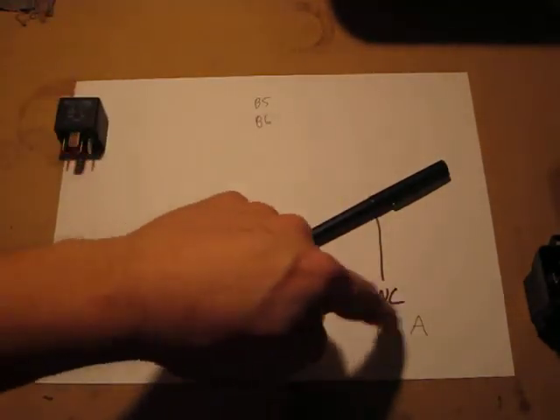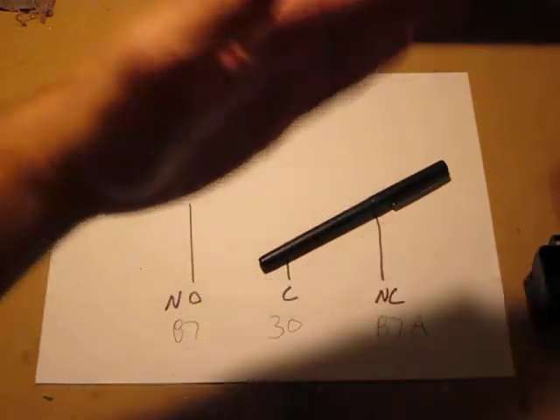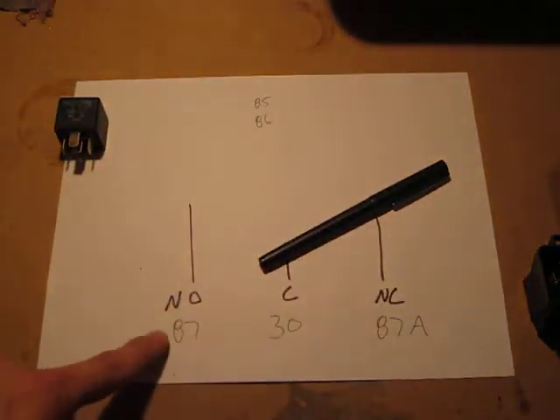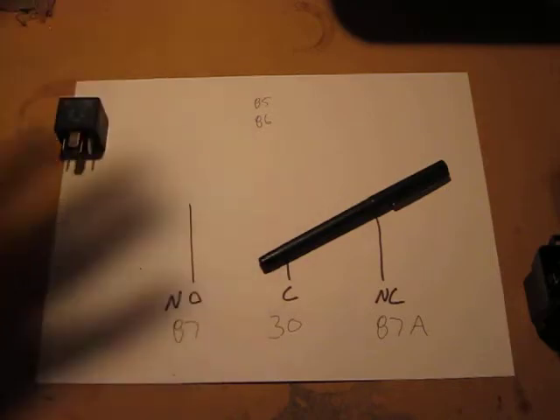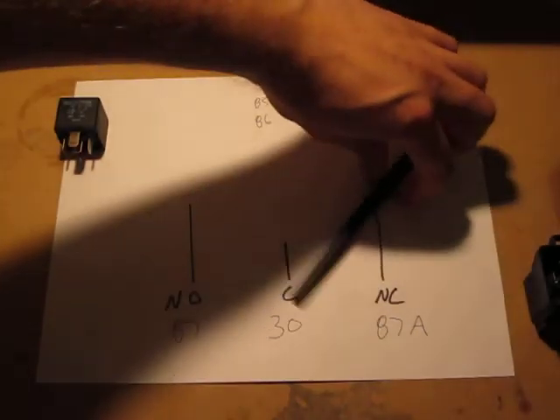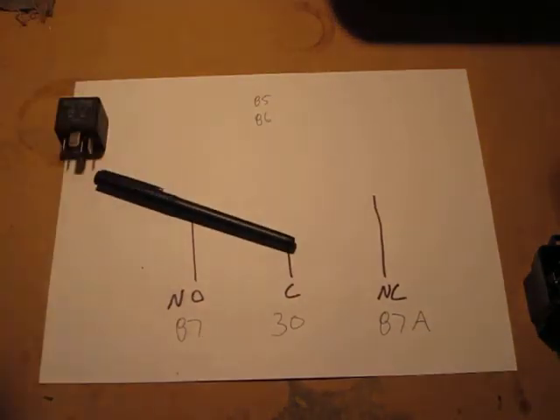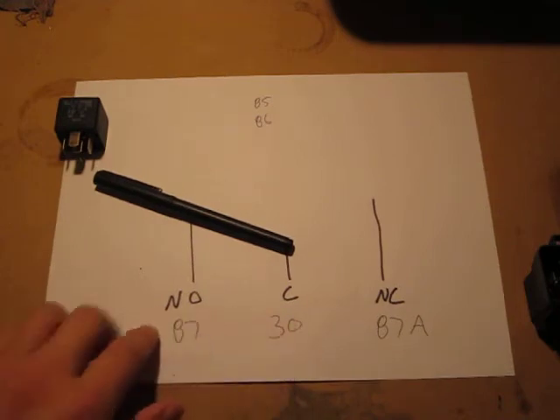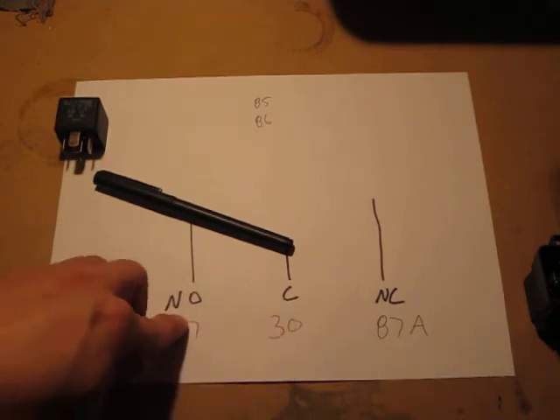So, normally closed, when the switch is in this position, these two are connected. NO stands for normally open, meaning it's not connected to anything. When you flip the switch, or you energize the relay, you now have connected what is normally open, but since it's energized, it's closed, to your common. Now, this side is open.